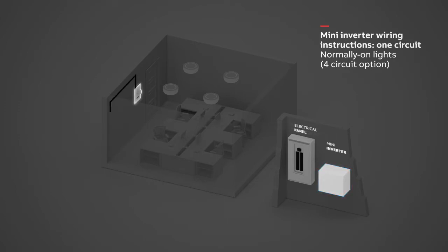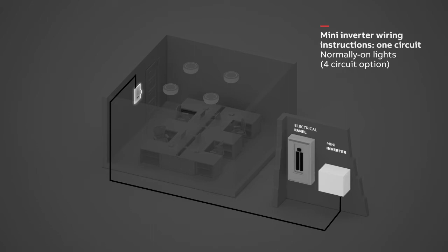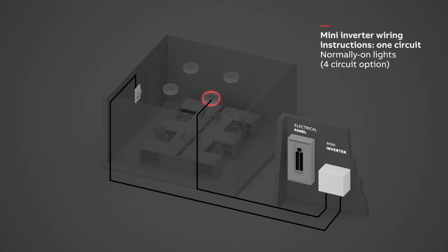Wire the 0-10 volt wall dimmer to the first input of the 0-10 volt dimming control terminal block in the Mini Inverter. Wire the first output of the 0-10 volt dimming control terminal block to the 0-10 volt dimming driver input of the lighting fixtures that will operate as emergency lighting.